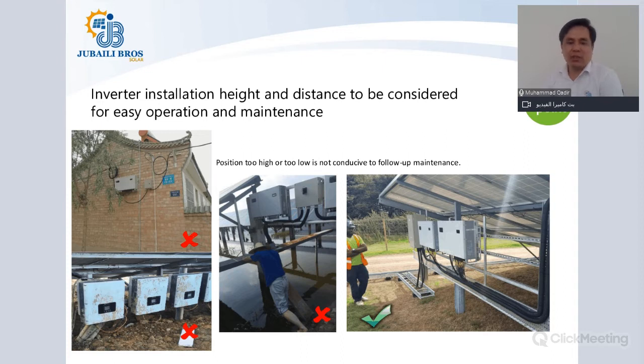On the right side in the picture, you can see the inverters installed, and the installer standing next to them can see the inverter very clearly. If any maintenance is required, he can take out the inverter easily. Maintenance will not require any special tool to go up very high, because it is very close to the person. The best way of installing the solar inverter is at a height where you can see the LEDs in front of your eyes.